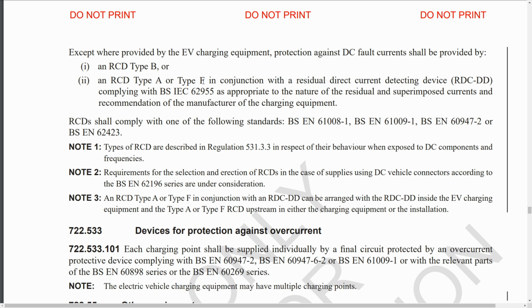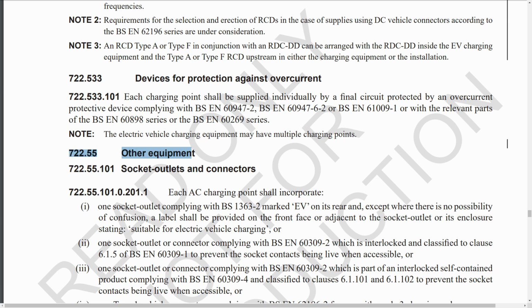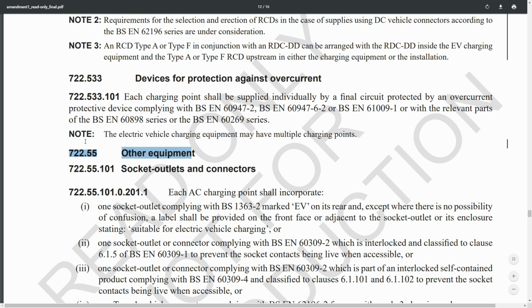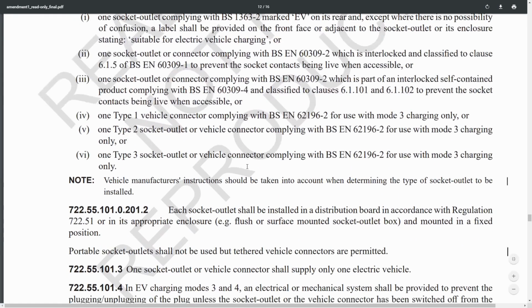So the type F one deals with the higher frequency currents there, rather than just the standard type A, which only deals with, of course, 50 Hertz. And this RDCDD is basically, as it says there, residual direct current detecting device. Previously that was just called appropriate equipment that provides disconnection of the supply in the case of DC fault current above 6 milliamps. So again, it's the same thing, it's just got its now official name added in there. Just before this here, there's a piece that's been removed, and that was isolation switching, which basically was a single part about emergency switching off. That's now been removed, so obviously no longer applicable.